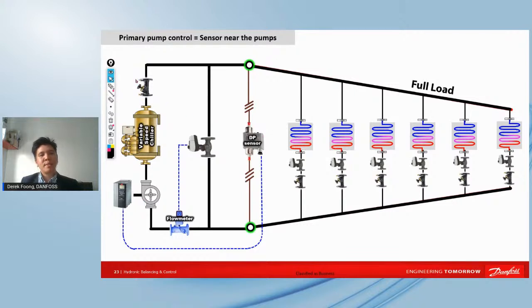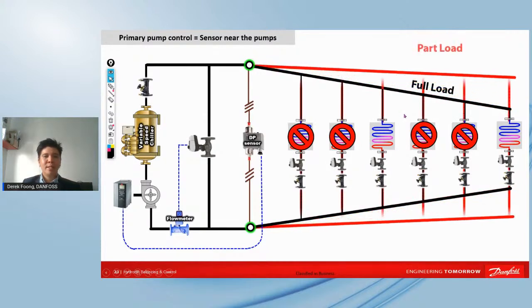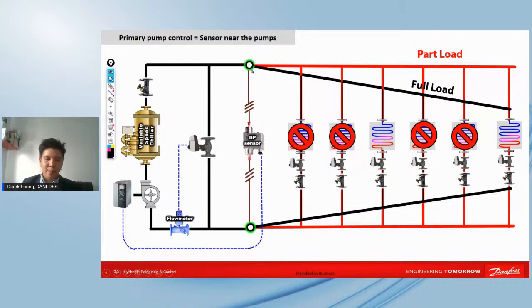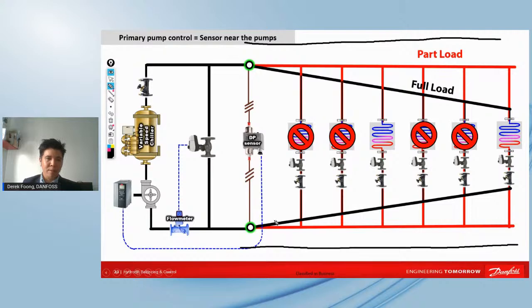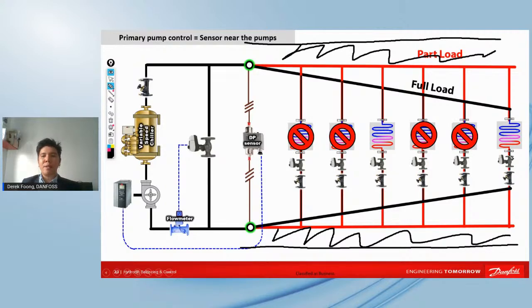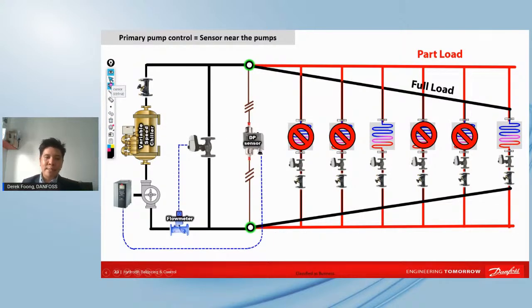Now, what is the system dynamic like, you may ask? Of course at full load, it doesn't matter where you mount the sensor, it's always the same. You have frictional losses when water travels around the system. Now, what happens if some of the units close and just a few are left open? Pressure does build up when you still have the sensor across the header. And yes, you may save energy, because if you compare this against no control, it is this area of pressure that we get to reduce. This is the other part of the pressure that we get to reduce. So you still get more pressure than required in some or most areas of the system during part load. It's not the most optimum, but at least we get to save energy.